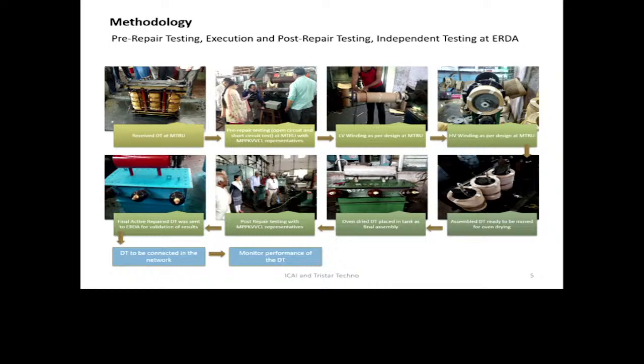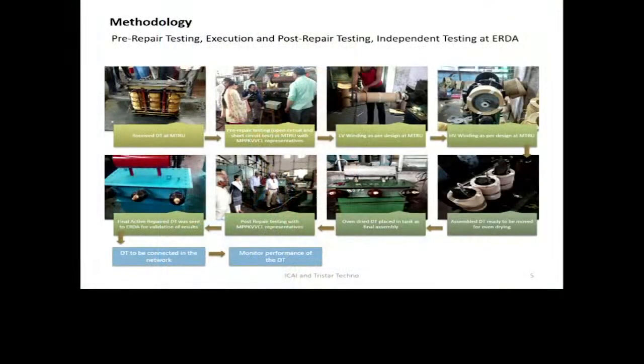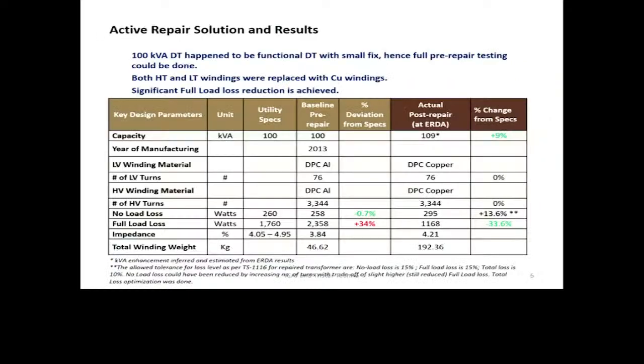So this is the first case with MPPKVVCL. This is what they have done for the repairing of the transformer. Before that, they took all the testing prior to repair. What were the design criteria mentioned earlier, before bidding the transformer tender, and what was actually found in the transformer? Based on that, they tested pre-repairing and post-repairing also, and it was certified and witnessed by ERDA.